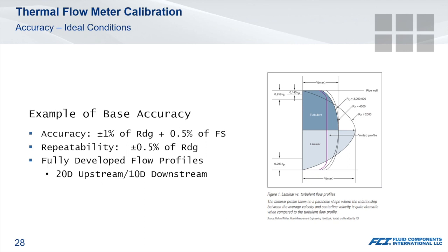Many applications don't require custody level accuracy, so why unnecessarily pay for that level of performance? The typical accuracy of a thermal meter is plus or minus 1% of reading with a repeatability of 0.5%. This level of performance has proven to be suitable for many applications in the process industries with the added benefit of a lower total cost of ownership.